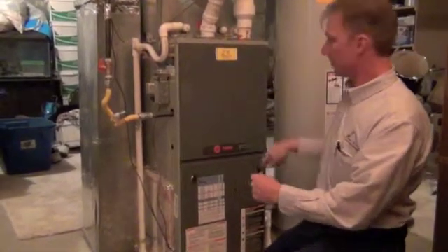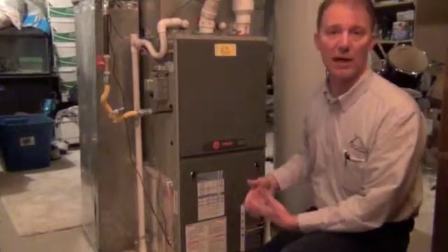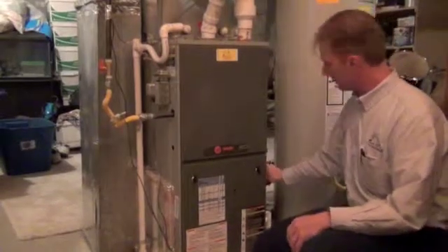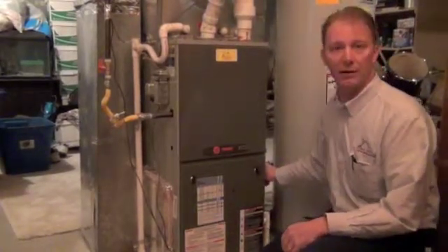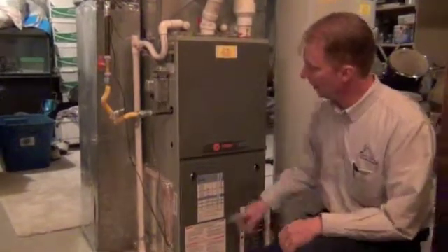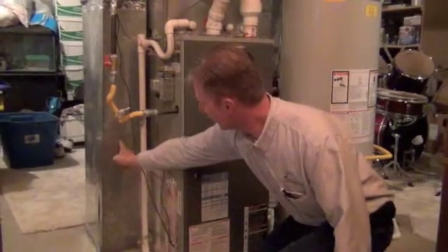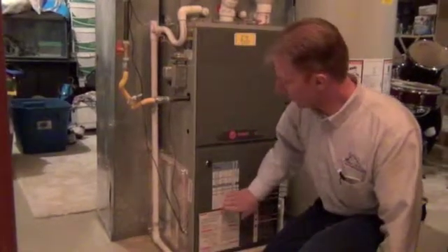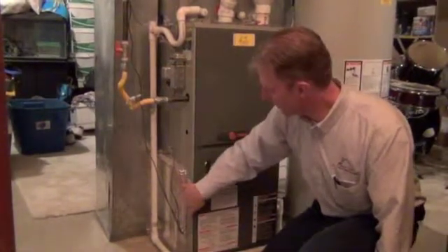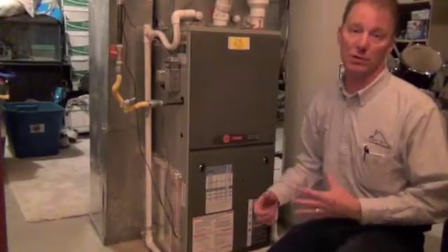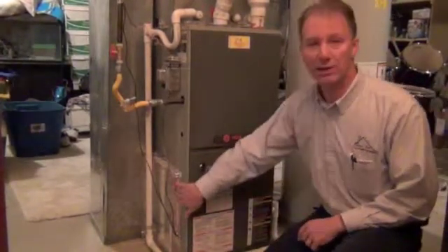Those are the return airs that come back to the furnace, and a lot of furnaces only have one of those on one side. Wherever that is, there's going to be a furnace filter located on the inlet to that, and it may be on the exterior, and it may be right inside this door right here. You can probably see it better on this side. You've got the return duct coming down, then we've got a filter located here, and then the air goes into the furnace. And so the filter is located behind this panel, and on this particular one it's accessed from the back of the furnace, so we're going to have to go around the back side to change this one. Most furnaces that you run into, though, you'll be able to access it right here from the front.